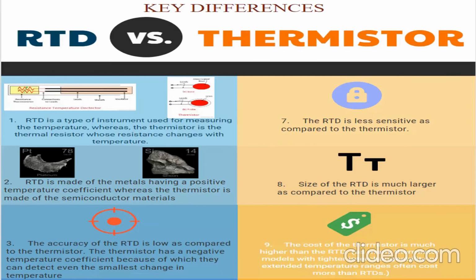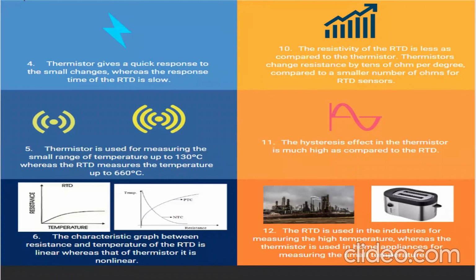And the cost of thermistor at times can be much higher than RTD. Even though RTD uses platinum, which is expensive, many thermistor models come with extended temperature range, which often cost more than RTDs. Thermistor gives a quicker response than RTD. Thermistor is usually used to measure small range temperature, while RTD is used to measure higher range temperature.